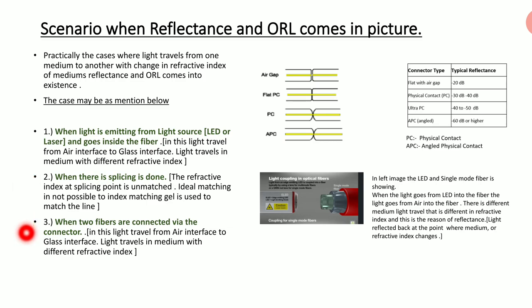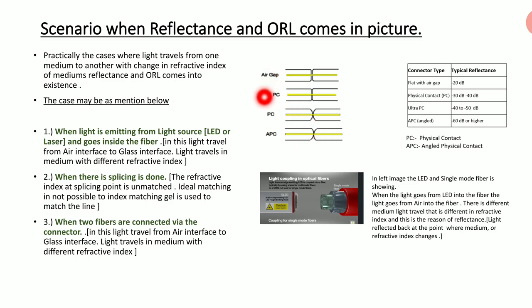When two fibers are connected via a connector, light travels from the air interface to the glass interface and back again — glass to air to glass. So reflectance comes into the picture. There are different types of connectors: air gap, flat, PC (physical contact), and APC (angle physical contact). Each has a typical reflectance value: APC gives minus 60 dB or better; Ultra PC gives minus 40 to minus 50 dB; PC gives minus 30 to minus 40 dB; and flat air gap gives minus 20 dB.